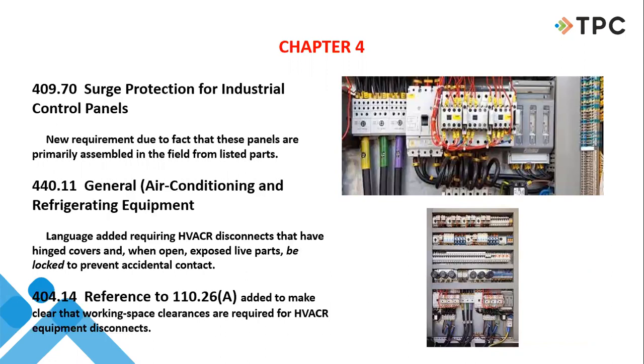Surge protection for industrial control panels is a new requirement due to the fact that these panels are primarily assembled in the field. All of the parts used to assemble them are listed parts, but they still want surge protection for the entire panel itself. Language added requiring heating and air conditioning refrigeration disconnects that have hinged covers, and when open, exposed live parts, be locked to prevent accidental contact. I guess because of the nature of the equipment, these types of disconnects didn't always have locking covers, and quite easily the wrong person for the wrong reason could get in there and expose themselves to shock hazard and or worse.